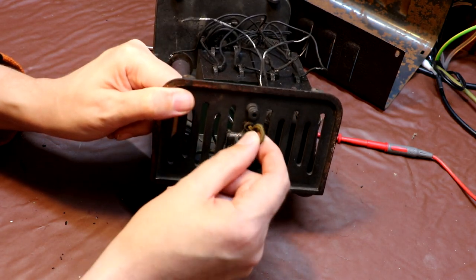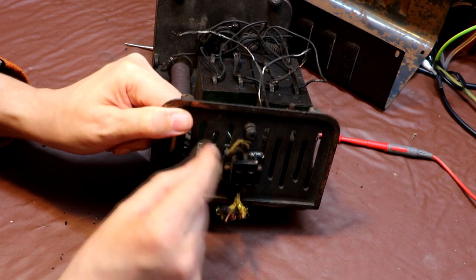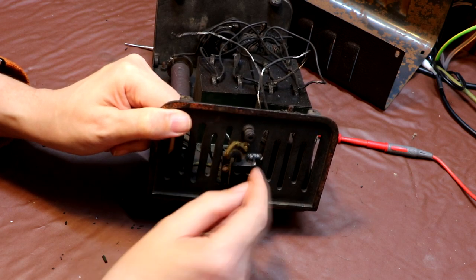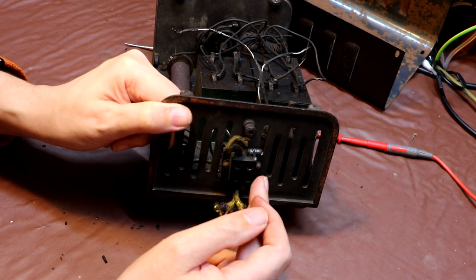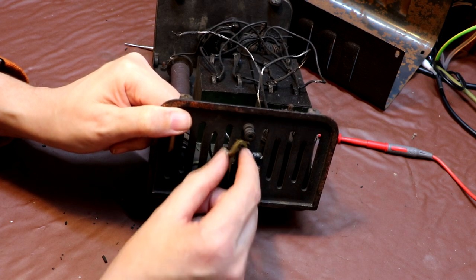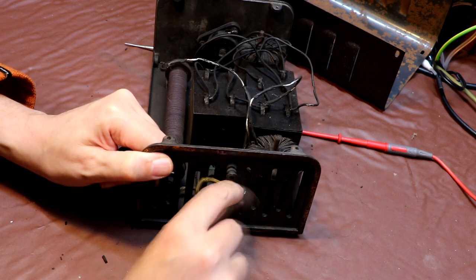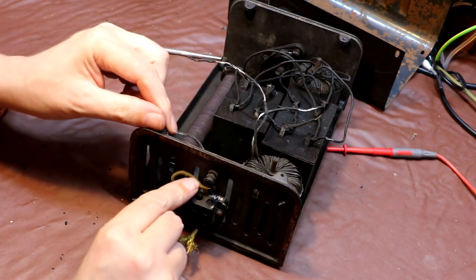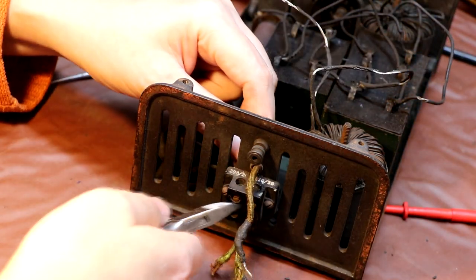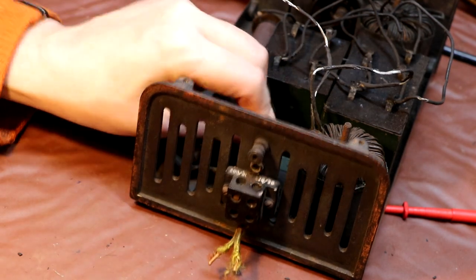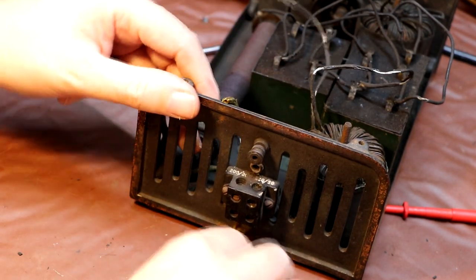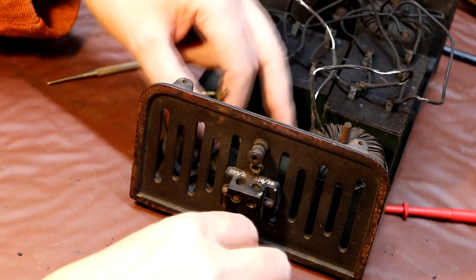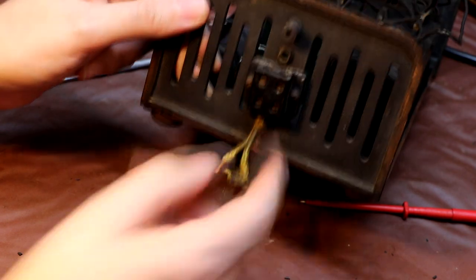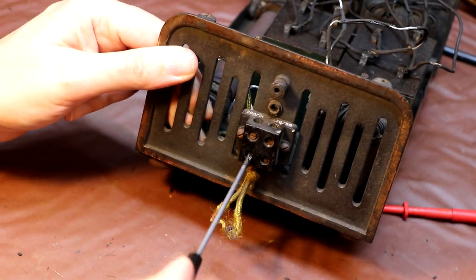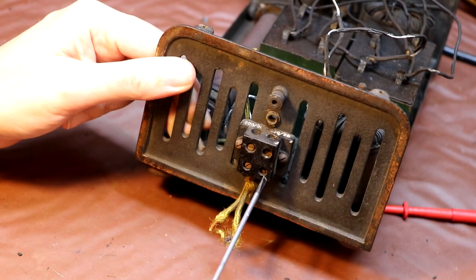And I think this is the neutral wire, and I think the idea is, depending on what voltage you want to select, it's got a stepped primary winding, so you can select from maybe, I don't know if it says on here. Unfortunately, I can't quite make out the writing. So I'm going to cut that. That's beyond use. So I think that was probably our neutral wire, but it wouldn't make any difference if it was live or neutral. And then on the underside of here, we've got two of our primary windings, our tappings.